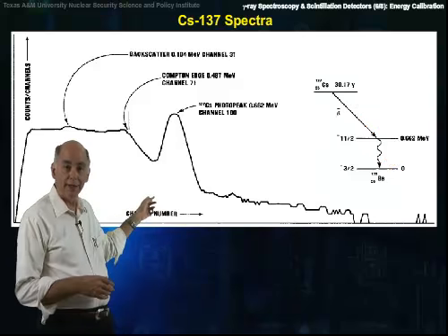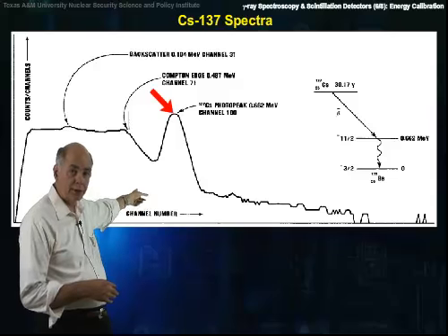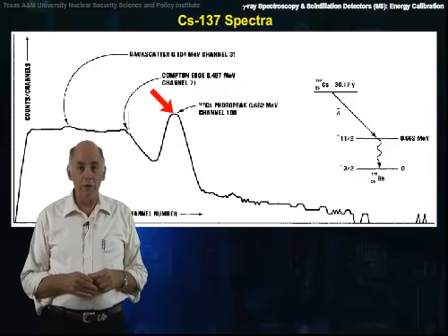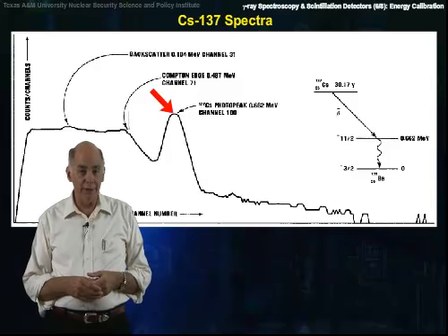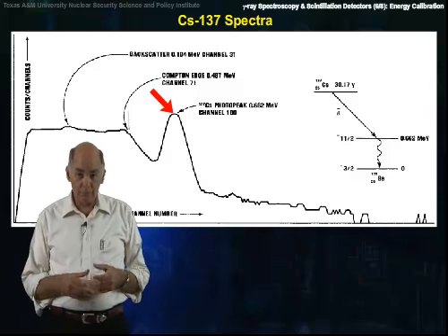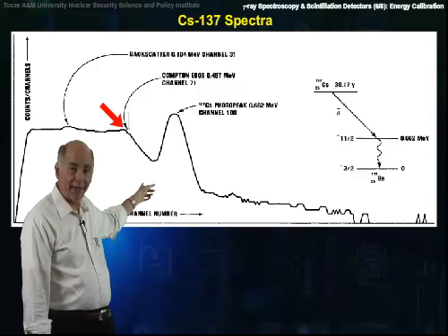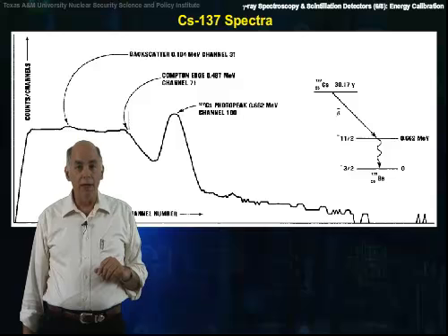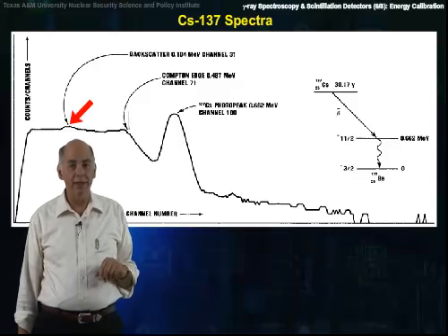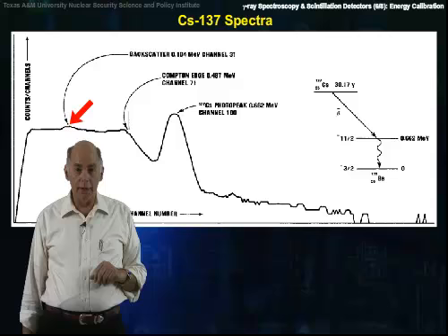Looking at the collected spectrum, here is the 662 keV photopeak, whose center is arbitrarily set to channel 100 of the MCA. We can locate the Compton edge at 487 keV and channel 71, and we can see a faint backscatter peak at about 184 keV.